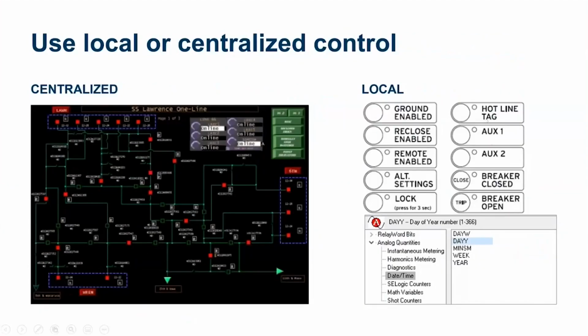So again, local control is very straightforward and easy, right? You can enable or disable reclosing by pushing this front panel push button, reclose enabled. So there is a push button on your relay. If you press that, it's going to enable or disable reclosing. But let's say you have multiple reclosers in your system. So it's almost impossible, if not very difficult, to go into all those reclosers and enable and disable reclosing individually.